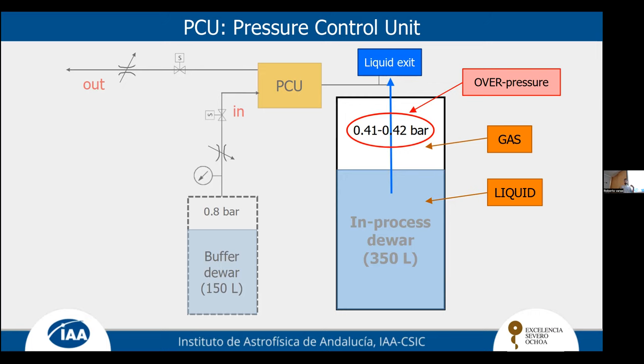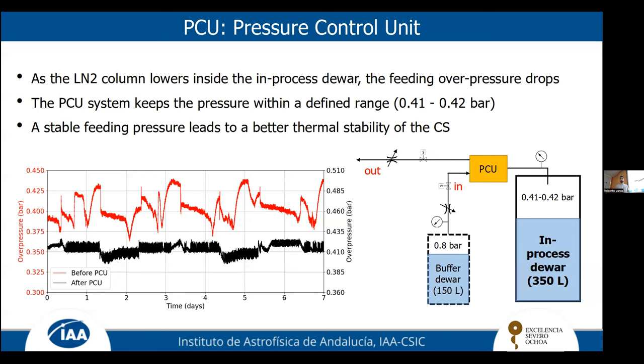We have, when the liquid is lowering, the gas volume is increasing, so the pressure lowers. In order to avoid this source of instability, because what we want is a very stable flow of gas to the system, we installed what we call the pressure control unit, which basically is in charge of keeping the pressure around 0.41 and 0.42 bars over the atmosphere.